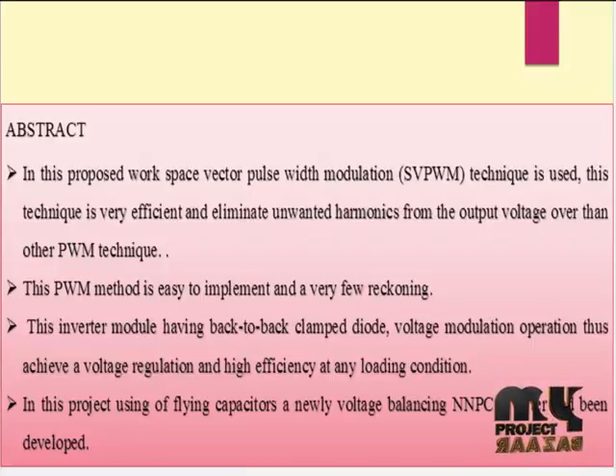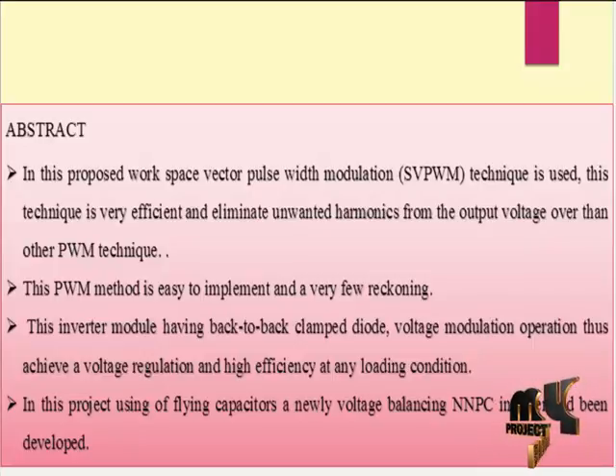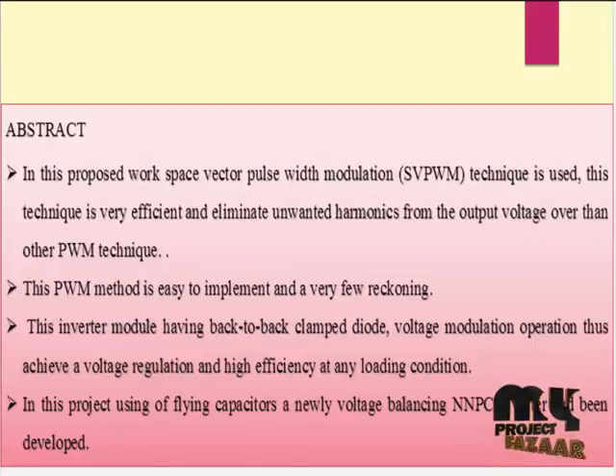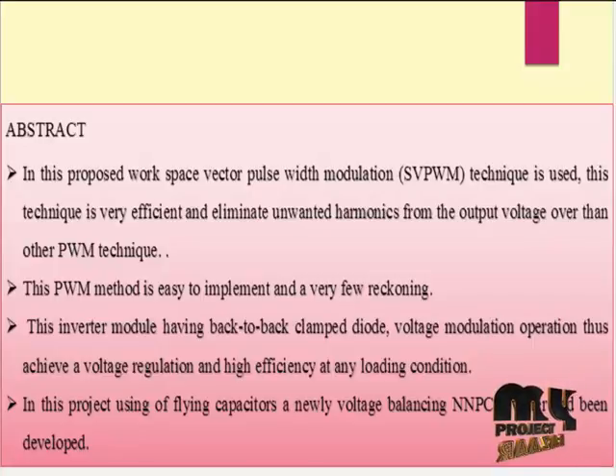This inverter module has back-to-back clamped diodes. Voltage modulation operation achieves voltage regulation and high efficiency at any loading condition. Multi-level inverters are very popular in medium voltage power conversion such as power motor drives, power conditioning devices, renewable energy generation and distribution, because voltage stress is less on switching devices, with better harmonic reduction, low switching frequency and less switching losses.